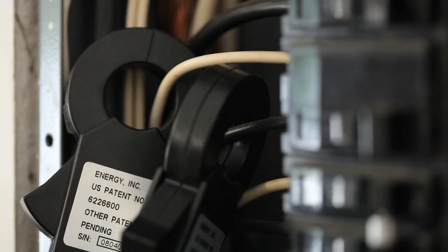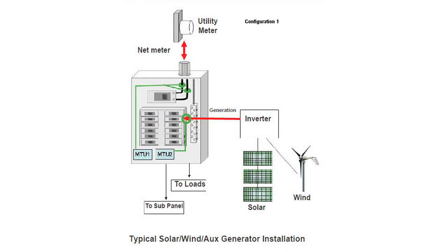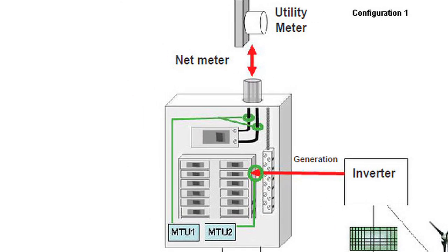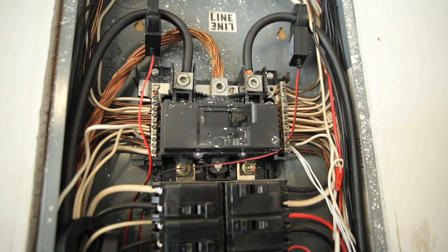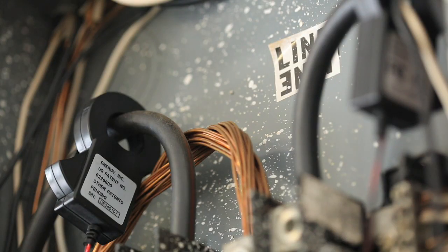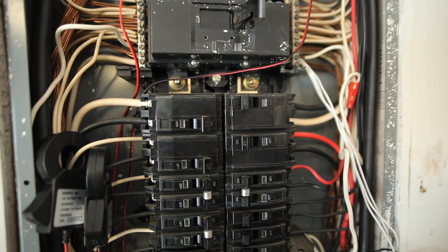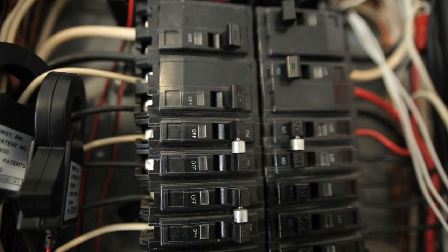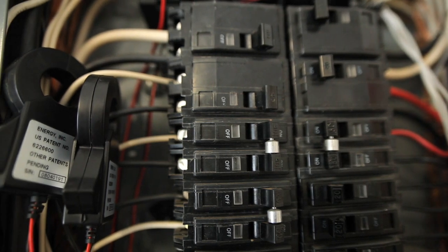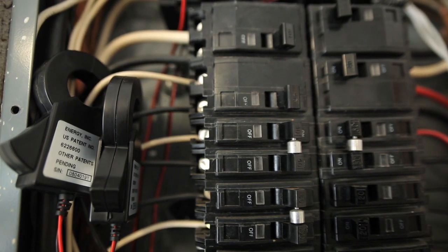There are three basic configurations for a generation system. The most typical configuration is shown here, where the source of generation feeds into a breaker in the main panel. In our example, measuring transmitting unit 1 is measuring power to and from the electric grid. The CTs are clamped around the main feeds from the meter, with the red polarity dots facing away from the breaker panel. The CTs of MTU 2 are clamped on the wires coming into the breaker panel from the generation source, with the red polarity dots facing away from the electrical panel toward the source of generation.